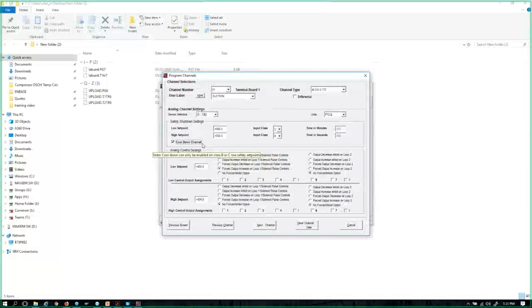So somebody might be asking themselves, well, what does the cooldown do? The cooldown is a way to where, if we want to shut the unit down for planned maintenance but we want to unload it first, we can have a group of channels that are disabled when we place the unit into cooldown. So from a running screen, we would push F2 and then enter to enter the cooldown, and a timer will start. In this case, from what we saw on the previous screen, 3 minutes.